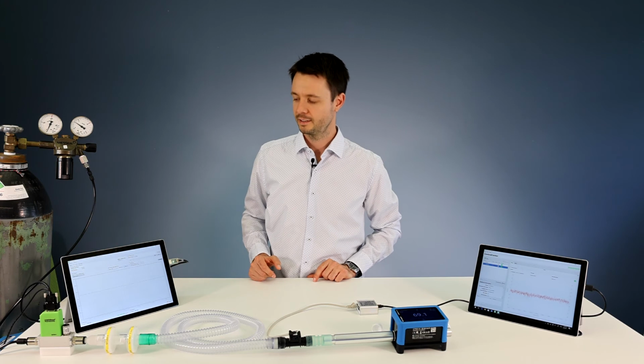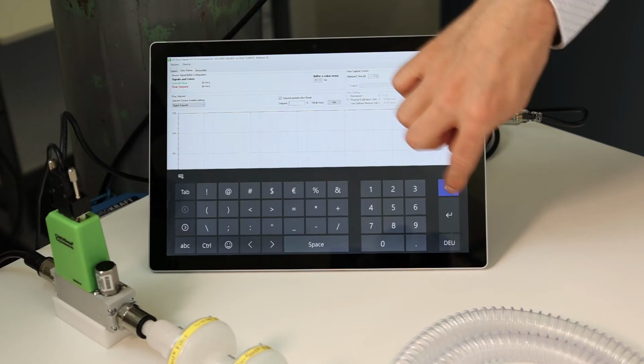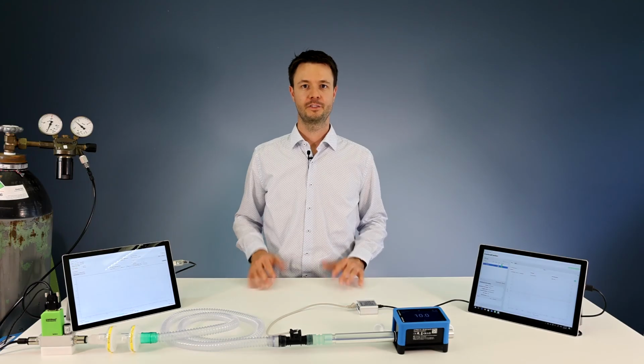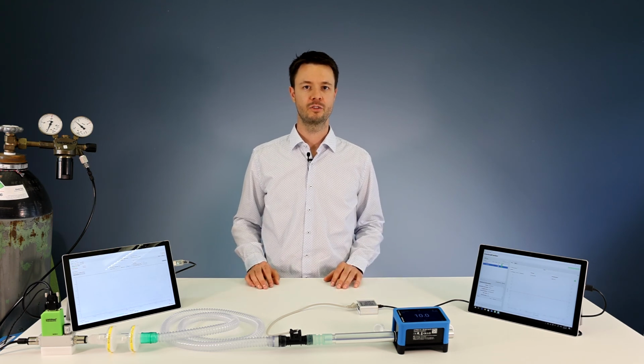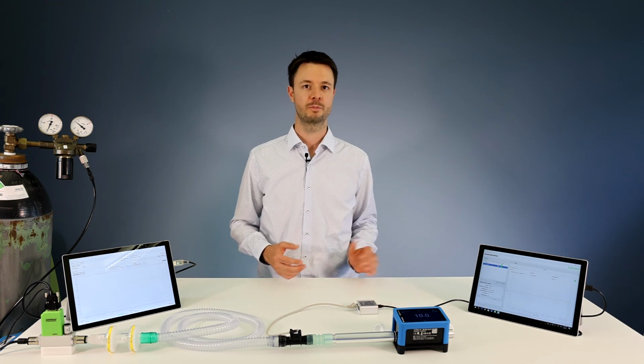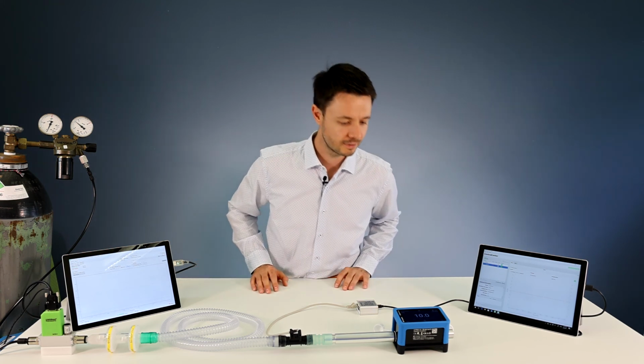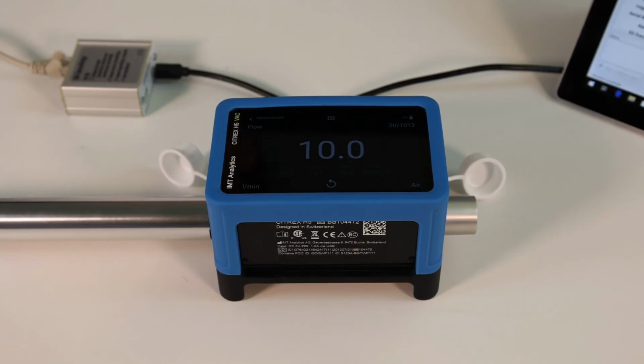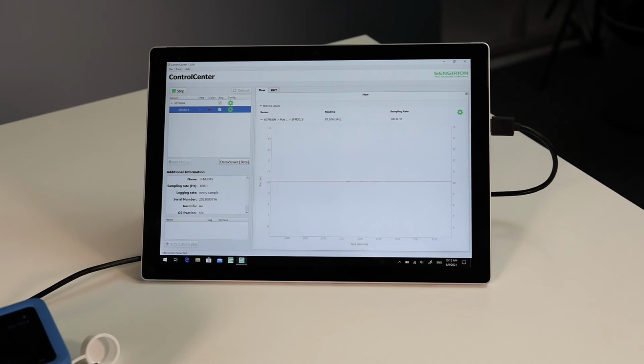In a real setup, and when evaluating prototype designs of your ventilator, it is very important to verify the behavior across the entire flow range. So let us repeat this measurement at 10 liters per minute, for example. With the same explanation as before, I would expect the flow sensors to read anywhere between 9.6 and 10.4 liters per minute. Is this also what we'll get? Yes, we're spot on! The reference is showing 10.0 liters per minute, and also the flow sensor is indicating 10.1 liters per minute. This means that we now have a setup with no turbulences affecting the sensors and an accurate flow reading over the entire flow range.